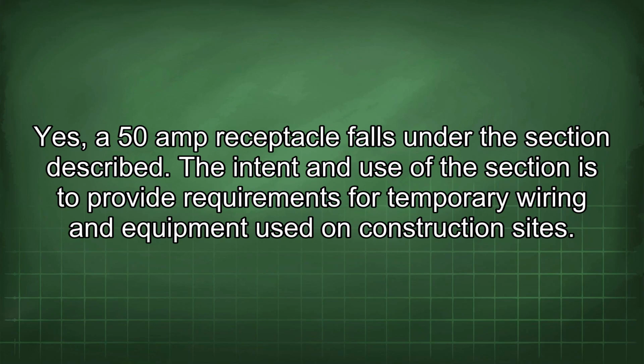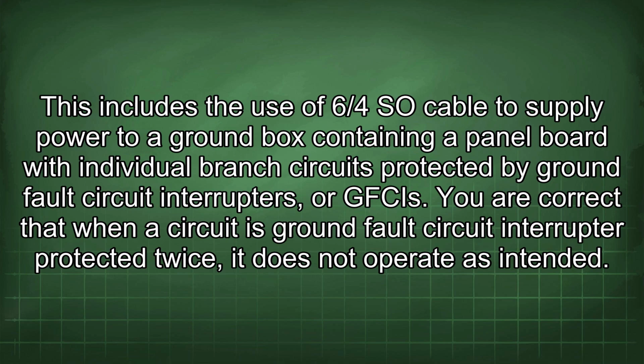Yes, a 50-amp receptacle falls under the section described. The intent and use of the section is to provide requirements for temporary wiring and equipment used on construction sites. This includes the use of 6/4 cable to supply power to a ground box containing a panel board with individual branch circuits protected by ground fault circuit interrupters, or GFCIs.